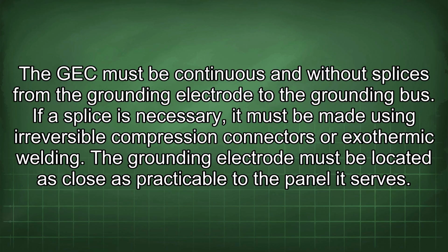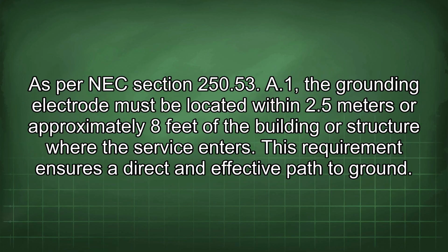The GEC must be continuous and without splices from the grounding electrode to the grounding bus. If a splice is necessary, it must be made using irreversible compression connectors or exothermic welding. The grounding electrode must be located as close as practicable to the panel it serves. As per NEC section 250.53 A1, the grounding electrode must be located within 2.5 meters, or approximately 8 feet, of the building or structure where the service enters. This requirement ensures a direct and effective path to ground.